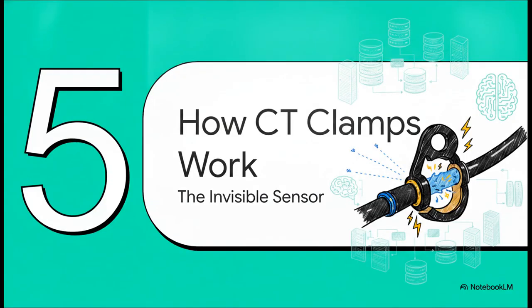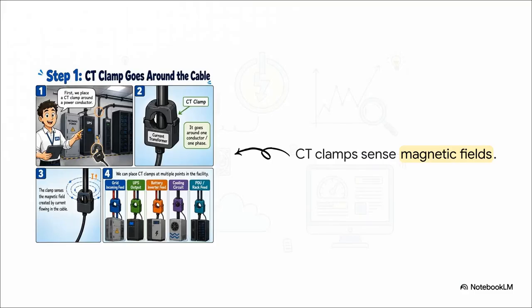And finally, part 5, how CT clamps work, the invisible sensor. But how does the software actually know this? You might be wondering right now, how on earth do we measure invisible electricity inside thick, heavily shielded cables without physically cutting them open to intercept the power? The answer is an ingenious little physical sensor called a CT clamp, like the Bentus eGauge systems used in these setups. A current transformer, or CT clamp, physically opens up and just snaps around a power cable. It doesn't even need to be wired directly into the electrical flow. Instead, the clamp simply senses the magnetic field that is naturally created by the current flowing through that conductor. By carefully measuring that external magnetic field, it precisely calculates exactly how much current is passing through the cable inside.